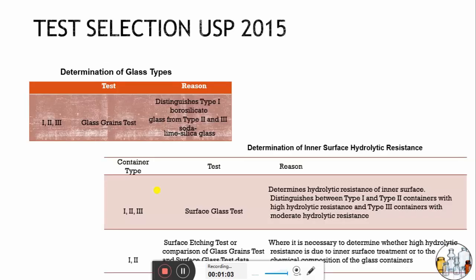Starting with selection of tests according to USP 2015. For determination of glass type, the first test is the glass grain test. The glass grain test is usually used to distinguish Type 1, that is borosilicate glass, from Type 2 and Type 3, that is treated soda lime glass and soda lime silica glass.